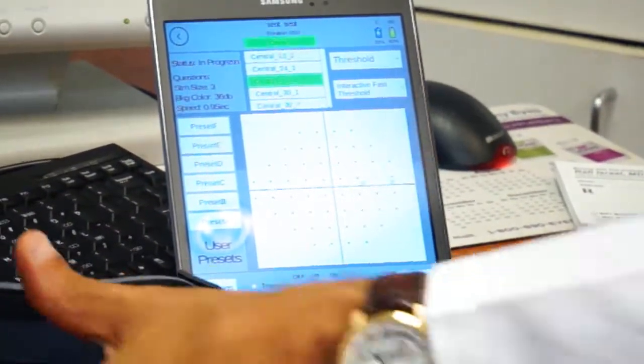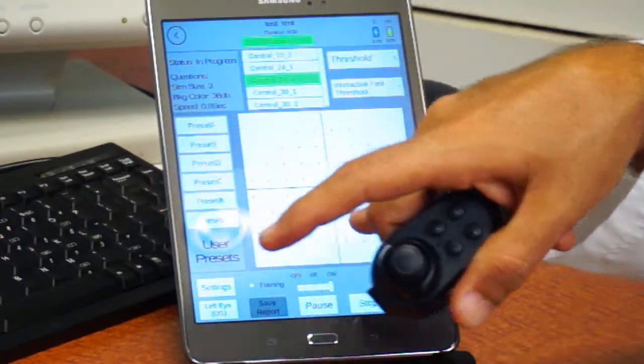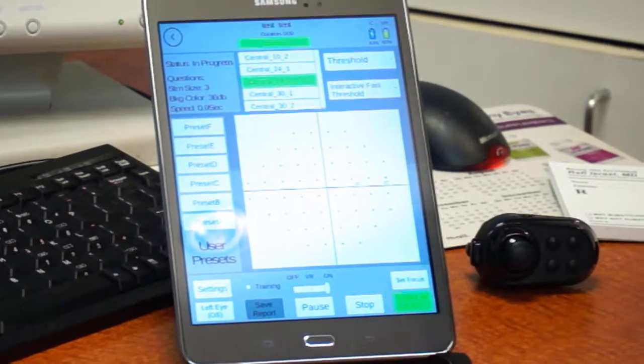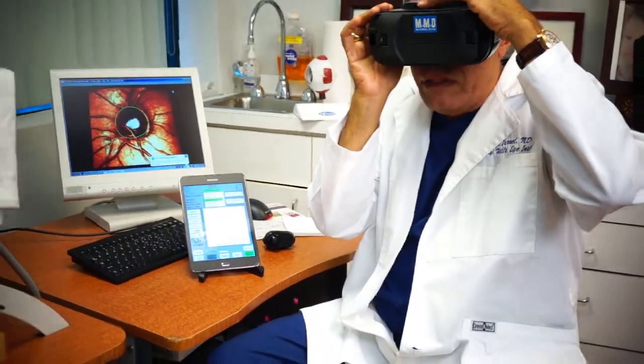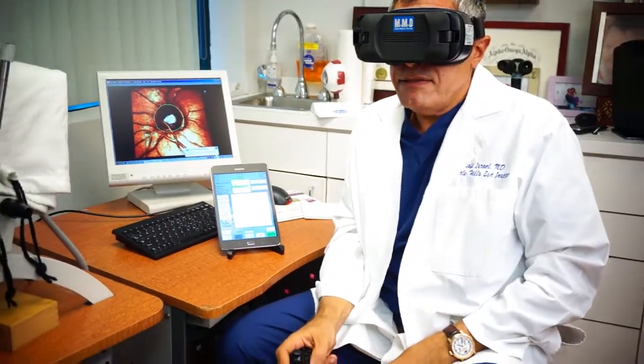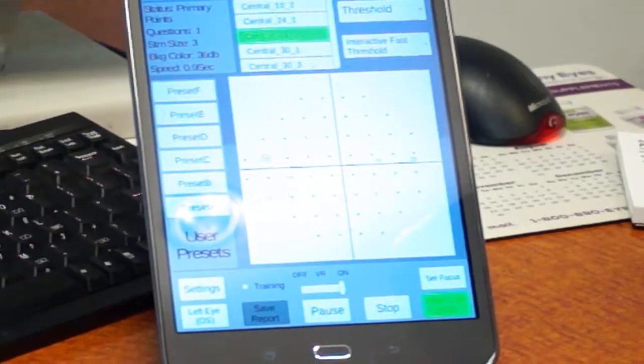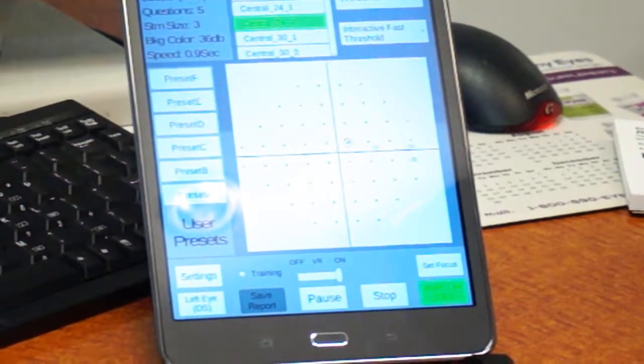And now I will attempt to take the test. And while I'm taking the test, I want you to pay attention to the controller and see what you see. So as I take the test, the operator should be able to see the location of the lights that are being stimulated and also the results and the amount of the stimuli. A normal test will take about three minutes to do a full threshold test.